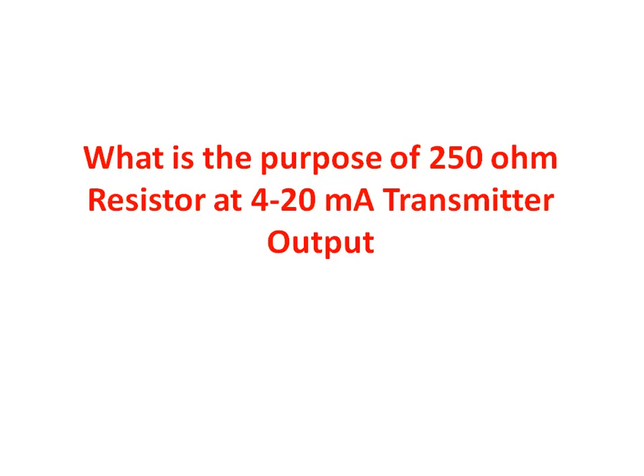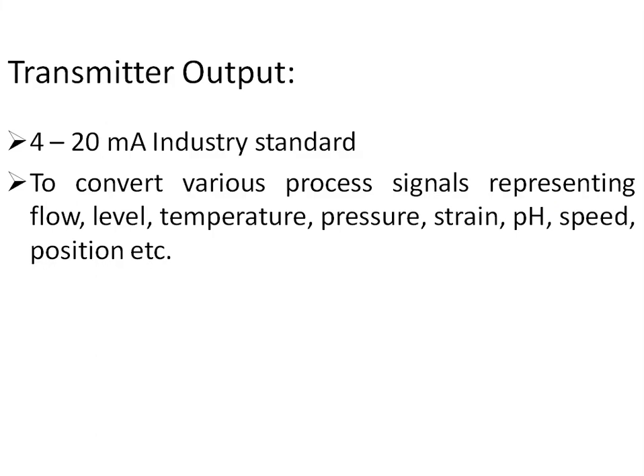In this video I will discuss the purpose of the 250 ohm resistor at the output of a 4 to 20 milliampere transmitter, or at the input of the receiver. 4 to 20 milliampere is commonly used as the output for a transmitter or transducer because it has the advantage of long signal transmission and high noise immunity. Various process signals representing flow, level, temperature, pressure, strain, pH, etc. can be converted into a 4 to 20 milliampere signal.